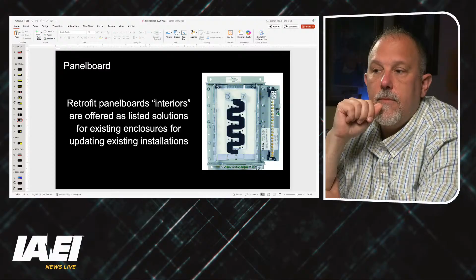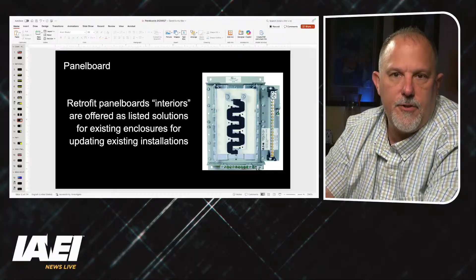Sometimes, most manufacturers of a panel board will make their own enclosures, but I could go to an enclosure manufacturer and put a panel board inside of it, as long as I have and follow the rules. Now, if it's a listed product applied and installed per the manufacturer's instructions, in 408, section 408.9, I have the requirements that help me understand how to apply that solution.